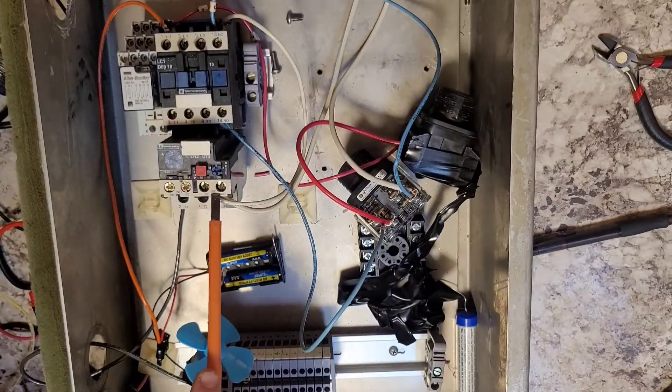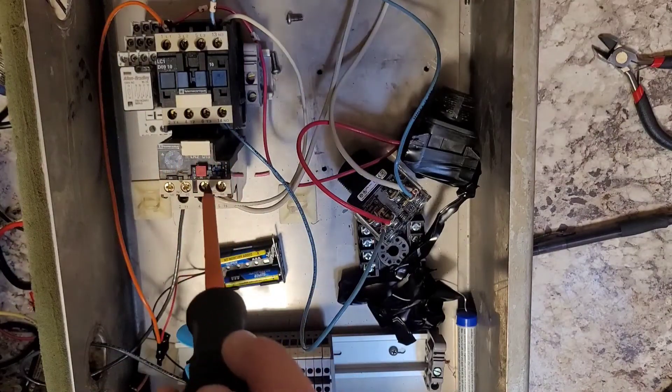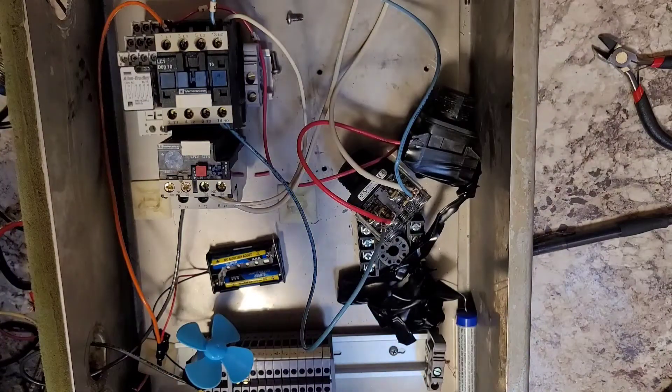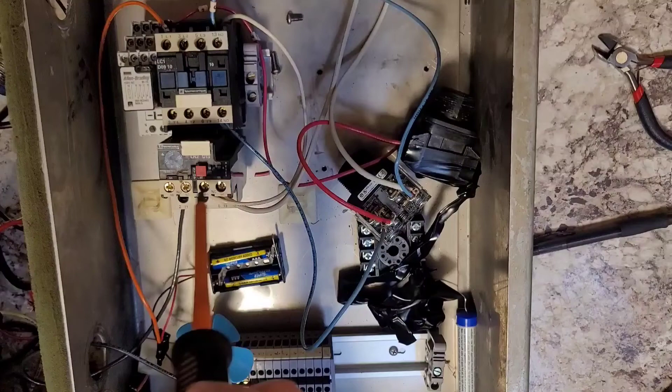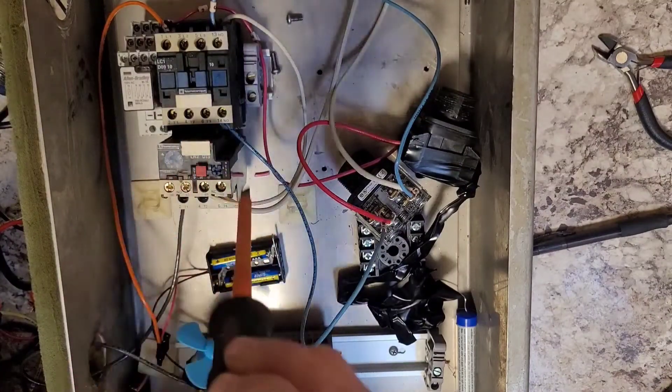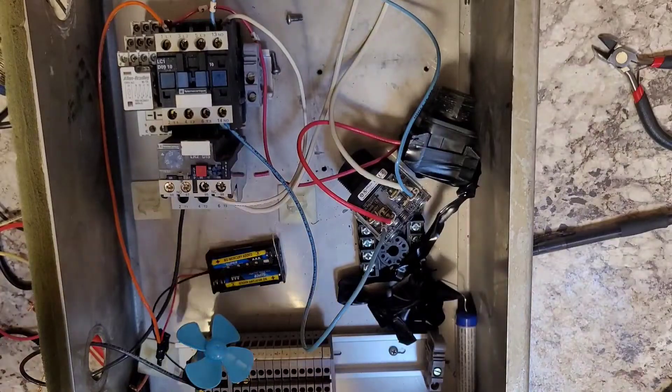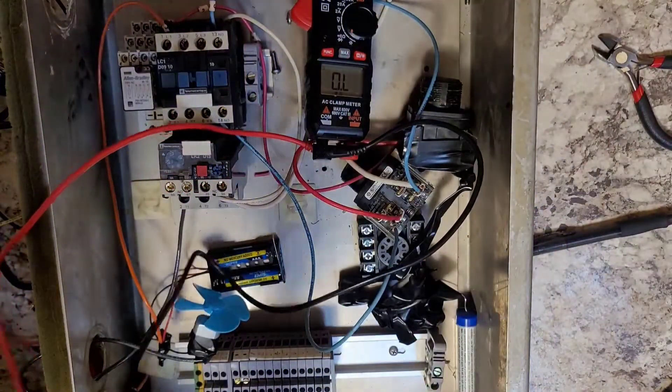This is not to be confused with the normally closed overload contacts. This unit down here opens up when the motor is running at too high of power. If something's wrong, this will open up. But this is the overload unit. This unit up here, this is your contactor, aka motor starter.